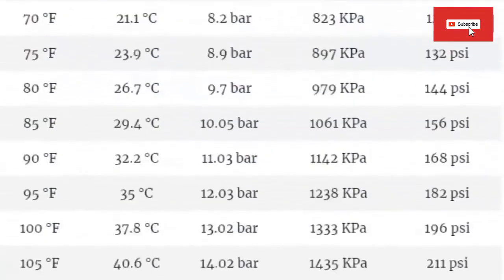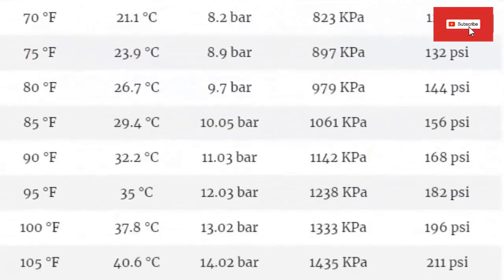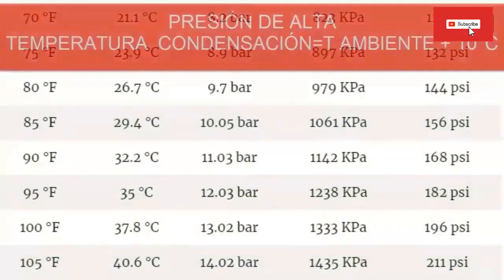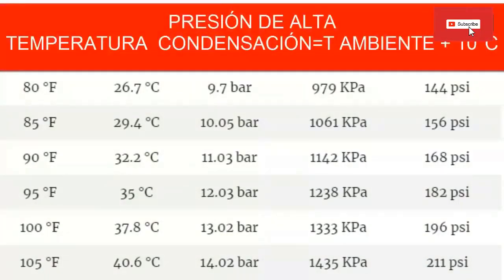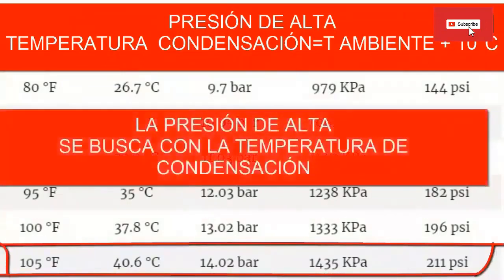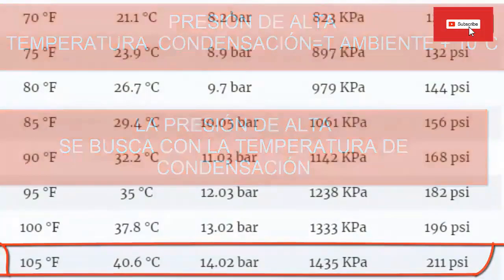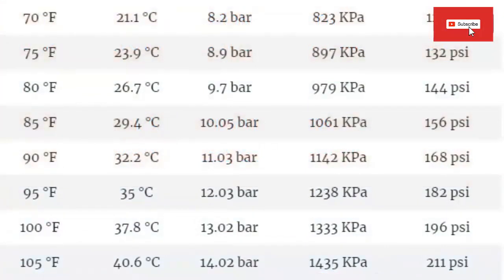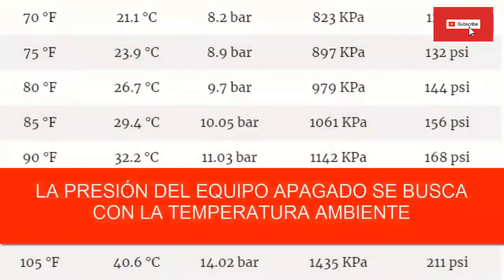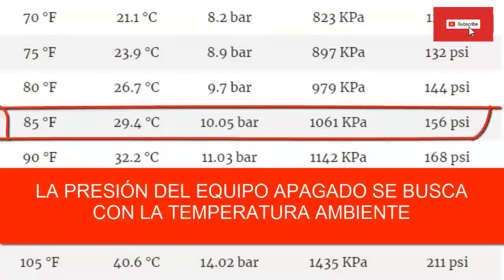For the high pressure, taking an external environmental temperature of 30 degrees Celsius as an example, we increase this value by 10 degrees Celsius and look in the table for approximately 40 degrees Celsius, obtaining a pressure of approximately 211 psi, equivalent to 14 bar. Another important pressure value is when the equipment is turned off: at 30 degrees Celsius room temperature, the table gives an approximate value of 156 psi.